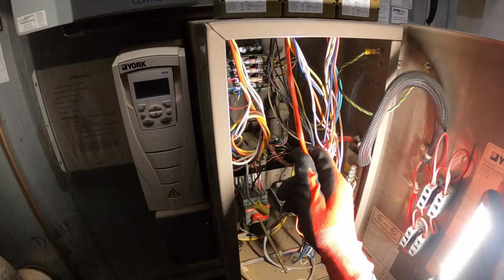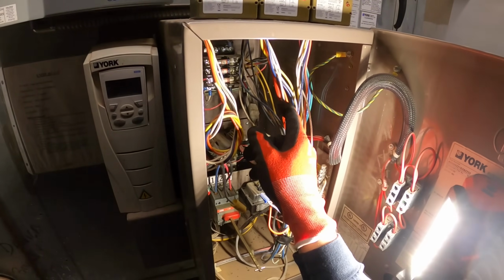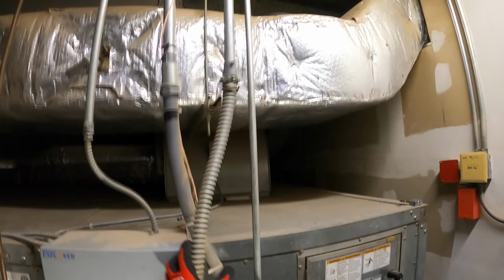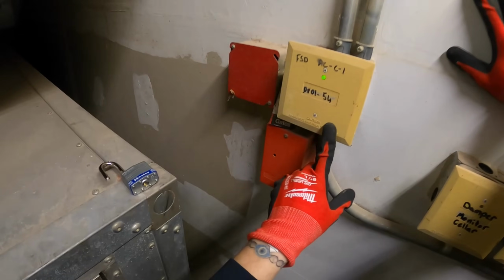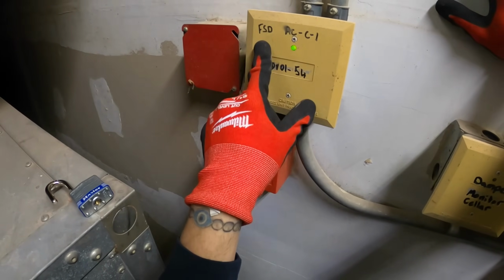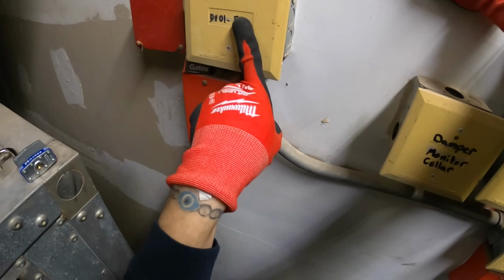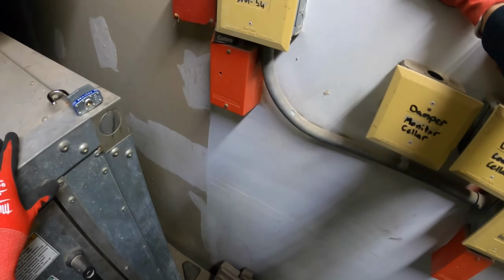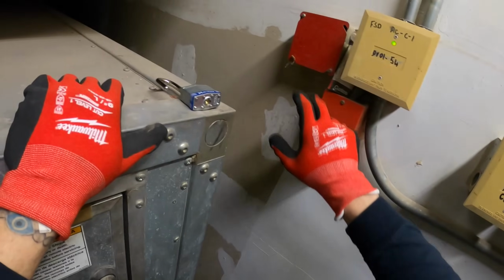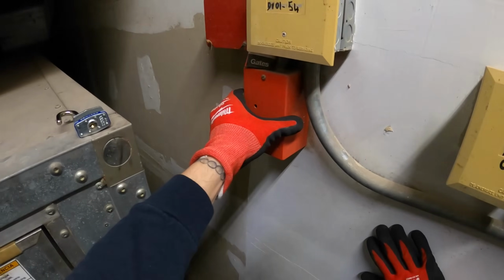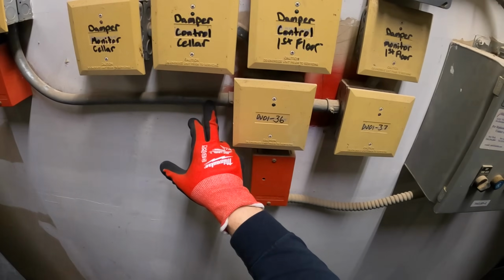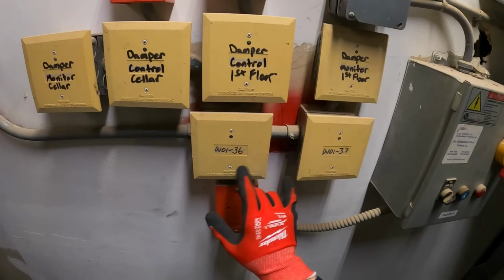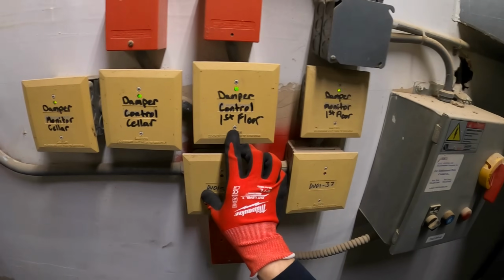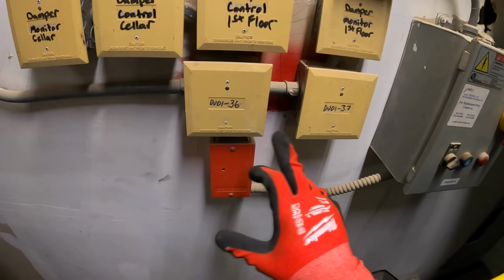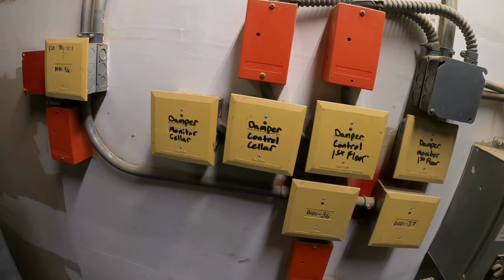This right here, so that's the fire alarm company. If there's a fire in the building, it's going to shut down this fan. Follow this. It goes into here, AC C1. This is the FSD. I see a green light. I feel like green usually indicates good. It's tied into these other, there's another relay here. Pretty sure that's a relay. And let's see, DDO-36. I think these are for other things. And then damper control. Everything is green. Everything's flashing green here, and that's a steady green.